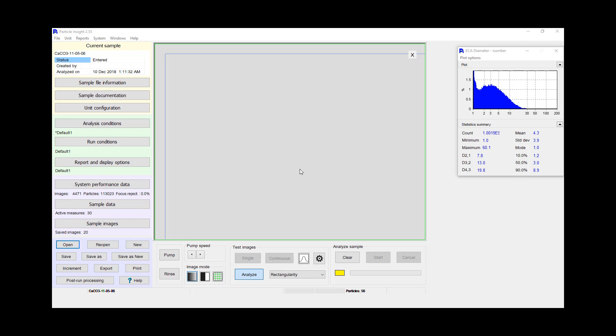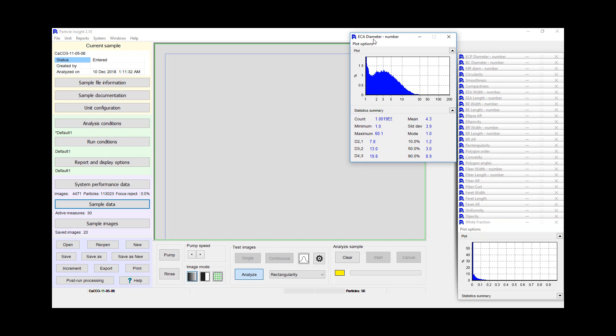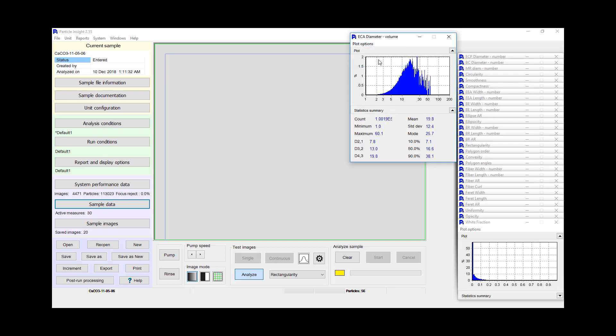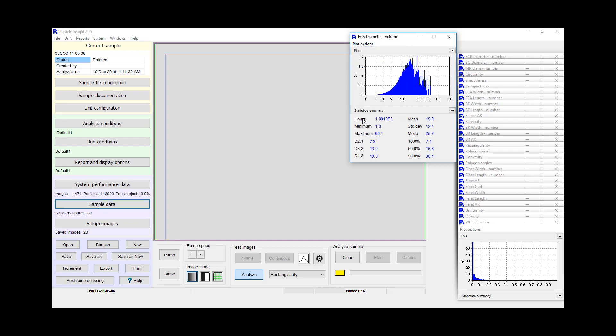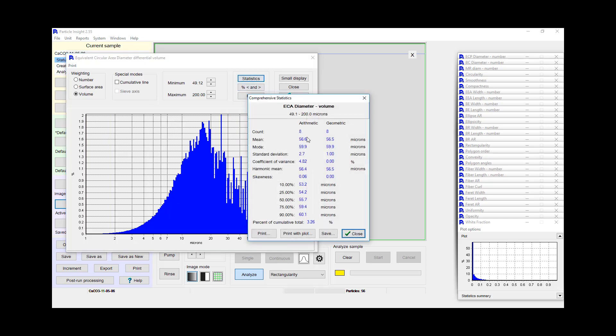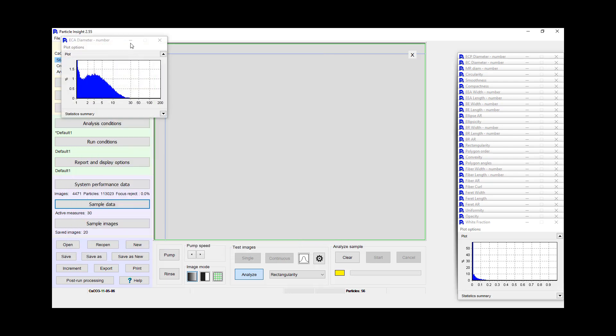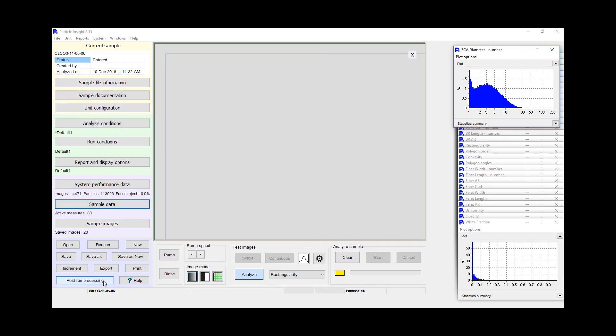So here we have a calcium carbonate sample that we can open. We have all the different distributions assuming particles are round. We can look at the number-weighted distribution assuming particles are round, or we can look at the volume-weighted distribution. We can look at specific numbers of particles. For example, if we wanted to find out how many particles we had greater than 50 microns, we can go to about 50 and see that there are 8 particles. We can also go in and see those 8 particles by going into the post-run processing.